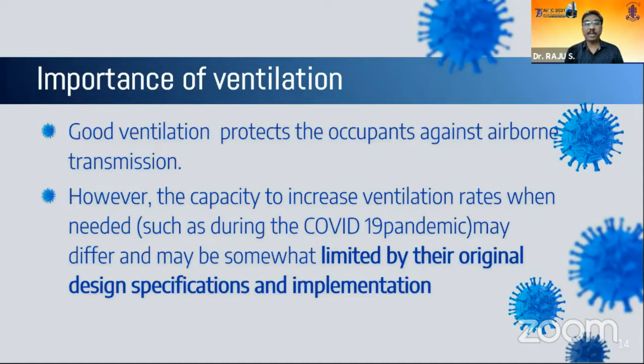However, we must understand that we cannot increase the ventilation rates as and when needed because it is limited by the original design specifications and the implementation. So how can we improve the air quality? Some of the things that we can do is to increase the ventilation rate, or what is called the air changes per hour. In mechanical systems, this has to be done by an AHU expert. It has to be recalibrated by them. We cannot meddle with that.